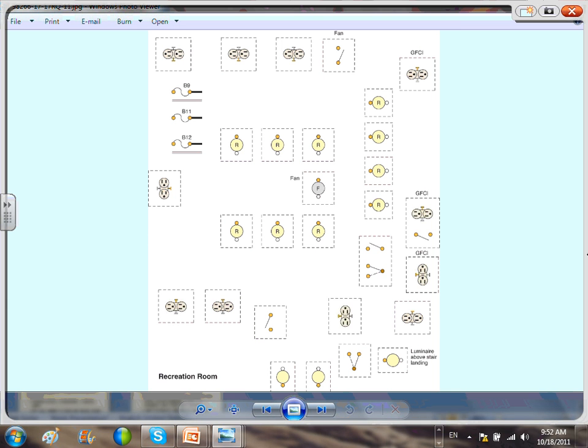Any question, guys, about wiring this? If I ask you, Chris, right now to wire this without the layout, and even reading, because this is a multi-wire branch circuit, you need to know which circuit went where, like these receptacles. When you ask me, where did this go? This goes to circuit one of the circuits, B9 or B11, but it really could be any one of them, unless you read through the description that they designed it for. Any question, guys, about multi-wire branch circuits? That's it for this.